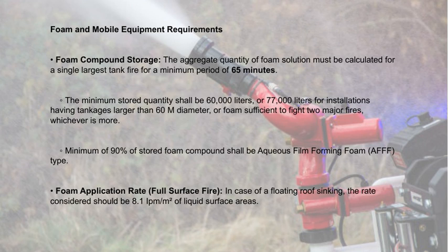Most of the foam stored, at least 90%, must be of the aqueous film-forming foam, or AFFF type, which is known for its excellent fire suppression capabilities, especially for hydrocarbon fires.